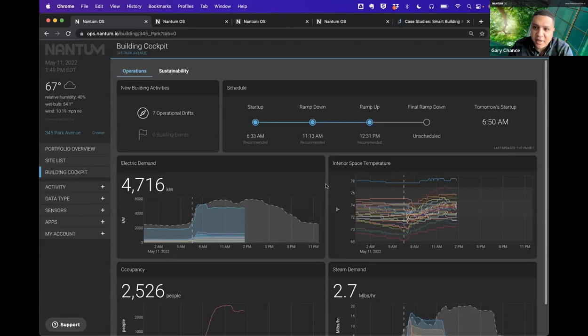This is what you're seeing for Nantum in terms of recommending or automating these different scheduled steps. So we recommended this morning the building start up at 6:33 a.m., ramp down for lunch at 11:13, a little earlier because the building's only about 50% occupied, ramp back up around 12:30, and then a final unscheduled ramp down, which will most likely happen as people leave the building earlier just because of occupancy levels. The general idea here is a quick view of what's going to happen across the BMS's automation for that day, and then diving in specifically to what we talked about earlier, the real-time energy management.